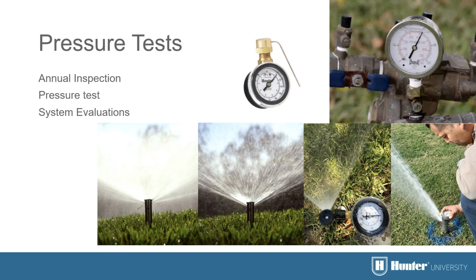So how do you guys check your pressure on a system, and what does a pressure test look like? Yeah, I know initially during construction, a design will say that the system's designed to provide X amount of pressure at so many gallons per minute, and the contractor has to verify. But after that job is installed and that pressure is verified, it is very common for the pressure to change. Typically the most common reason is development in a local area. As development increases, pressure is going to decrease.